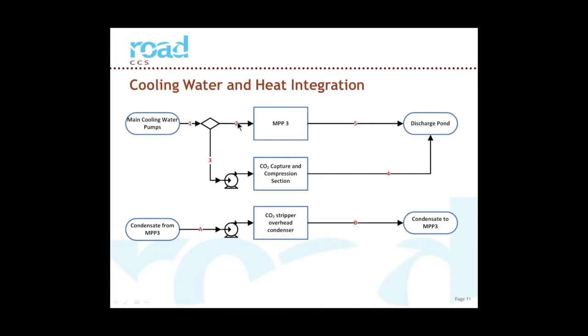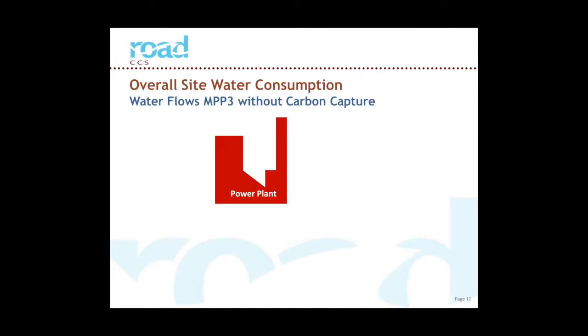So now I'll give you the numbers. First of all, the power station. So it requires a fair bit of demin water. It's a once-through supercritical plant, so it runs on very high purity water. It's slightly unusual in that it doesn't have a main water treatment plant on site. Rotterdam's very industrial and there's lots of plants in the area. And in fact, the demin water is bought in over the fence. That turned out to be cheaper. And then there's a polishing unit that brings it up to the quality required for a supercritical plant. So the demin water actually comes over the fence.